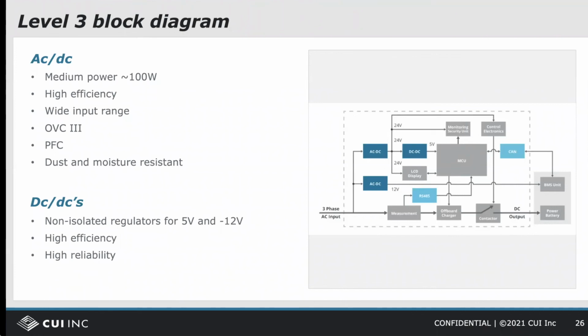A standard universal input power supply can only accept an input to about 264 volts. To operate off of a three-phase 480 volt input, the power supply must be designed such that it can accept a nominal 277 volts with some margin. Wide input power supplies can usually be found that are rated for 305 volts for 480 volt applications. Level 3 equipment also tends to be much larger than others. It's higher power and has more features, but also doesn't need to fit in your home garage, so the power supply isn't as tightly constrained size-wise. DIN rails and metal enclosed industrial power supplies are common choice for the 12 volt and 24 volt rails.